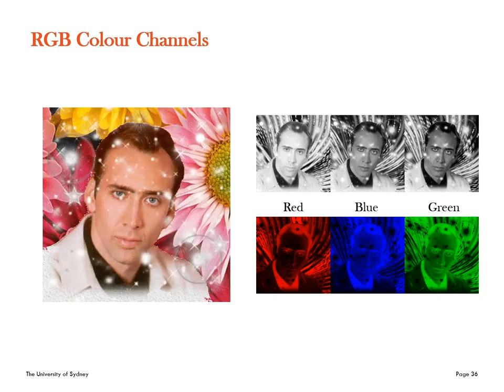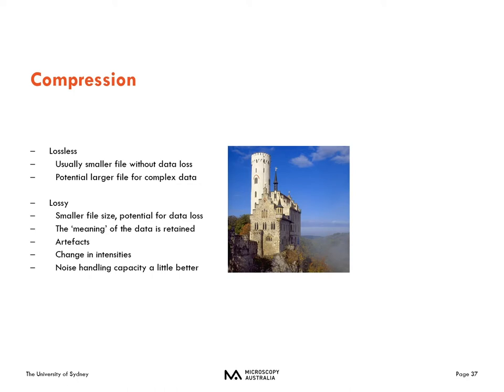Now let's talk about file formats. There are many different ways to save your files following acquisition. The main way should be to save your data using the proprietary file format of that software package. This type of file is always lossless — it has all the information in the image and is quite large in size, however it is smaller than a comparable TIFF format. Please do not save your data in a file format like a JPEG which compresses the file before saving. This type of file is called lossy as it actually throws away data contained within the image.